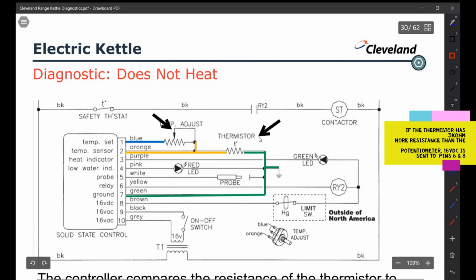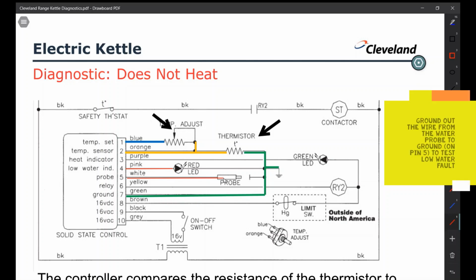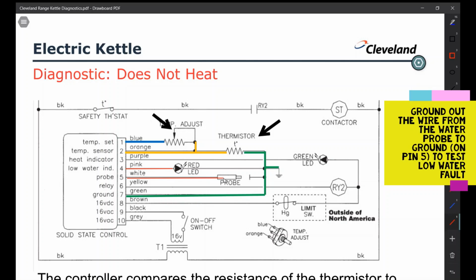If the thermistor has 3k ohm more than the potentiometer, 16 volts DC is sent from pins 6 and 8 to the RY2 relay, meaning that our red light is not on for our probe. Okay, so as long as we don't have a low water situation on the water probe on pin 5. If there is no signal on pin 5, the red LED will come on, indicating a low water error.